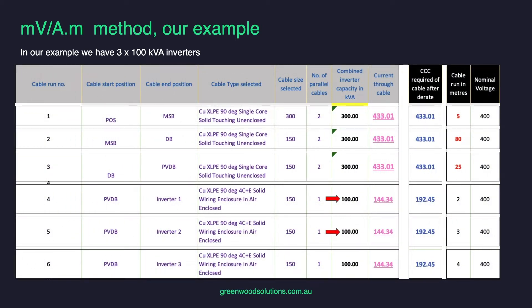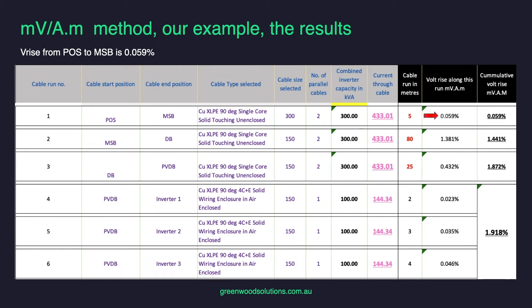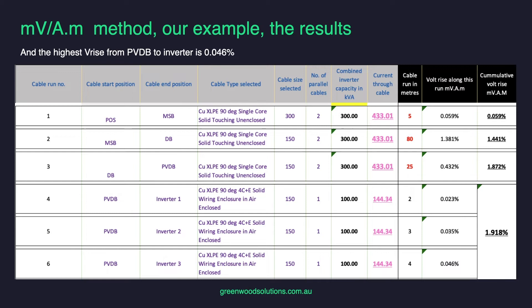In our example, we have three 100kVA inverters. There's a cable to the PVDB, then to the DB, then to the MSB, and then to the point of supply, as seen in the table below. Cables also have to be selected on their CCC — current carrying capacity. In this example, some parallel cables have been used, with current equally distributed between them, which is reflected in the V rise results. The V rise from the point of supply to the MSB is 0.059%, MSB to DB is 1.38%, DB to PVDB is 0.42%, and the highest V rise from PVDB to the inverter is 0.046%, resulting in a total V rise of 1.918% for the total run.